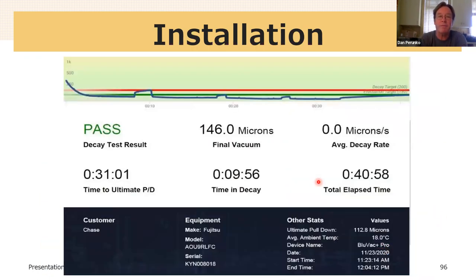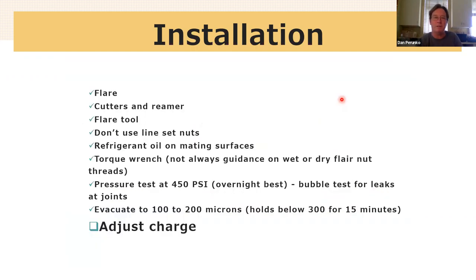And this is just a graph of that process. So this blue line is the microns and you'll see someone shut a valve here and the numbers started to rise. And so they opened the pump back up and let it pump. And you can see the next time they checked, it was much lower. And then they checked again, it was much lower. And then they actually shut the valve off and let it go through the decay test. And you can see in the time window where they're doing the test that it's only come up a little bit. And that's what we're looking for.